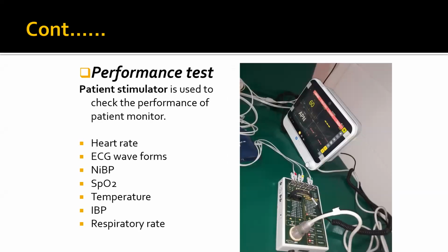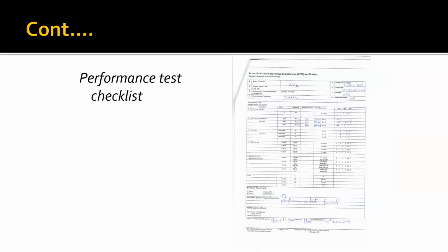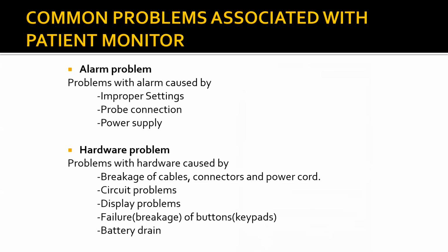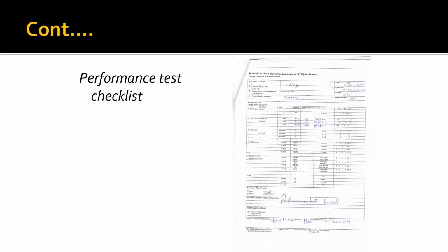When you do performance tests, you're going to check the ECG rate, respiration, NIBP, SpO2, temperature if you have a temperature testing connector, then IBP if you have an IBP testing probe. This is what the performance test checklist looks like. All the parameters are there according to the SimCube checklist. This particular checklist follows the SimCube performance test, so you can change it according to your simulator as well. You need to do the low test, actual reading, then the high test, and you check whether the alarm is working with ECG, respiratory, all that.